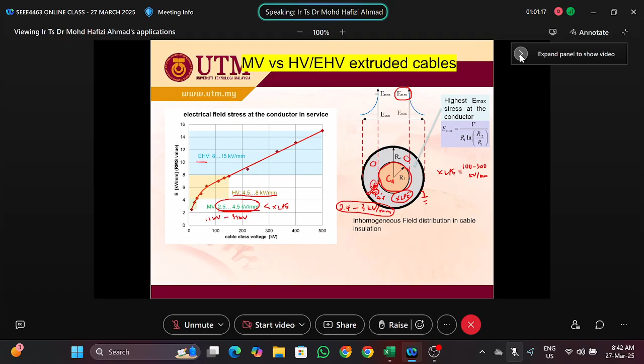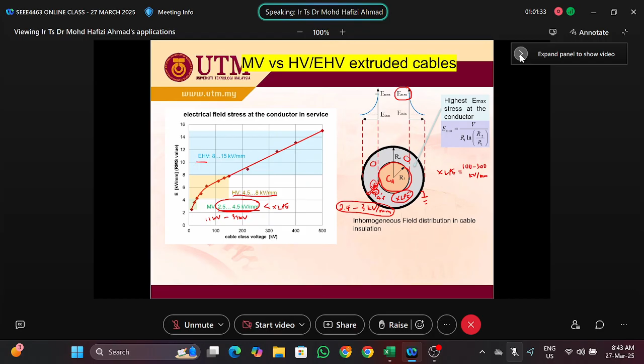So electrical tree is a conducting channel. It can conduct the current. And then finally, it may bridge between the high voltage conductor and the ground, and the current might flow. And this is called a short circuit current, and the flashover, the breakdown may happen. Okay, so this is something that we need to prevent from happening. Okay, so that's why all cables should be tested first. They have the routine test, and then we need to monitor and identify their quality. Okay, so this can be done by partial discharge technique, partial discharge measurement, and we will learn this in chapter 5.